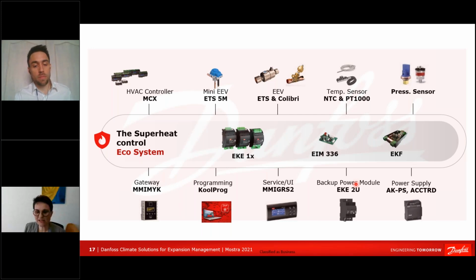There are lots of questions coming about which temperature we can use the ETS valve up to. I think we fixed most of them. A question was, can we use them up to 120 degrees Celsius? The reply we have is yes, it can stand up to 120 degrees. Some variants of the expansion valve are available for high temperatures, for hot gas bypass. But I have to dig into this one, because not all the valves can do that, and I think you need a specific version of it. Yes, exactly.